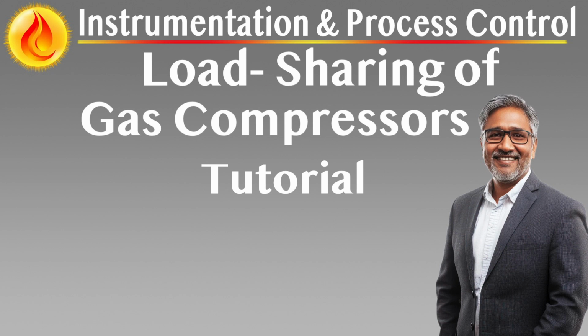2. Predictive rate-based response, POP, detects rapid changes in the control variable by comparing the instantaneous value, CV, against a filtered average, CVFG. The predictive deviation DevPop is computed as DevPop equals CV minus CVFG minus SPPop. If DevPop is positive, i.e. pressure is rising or falling faster than allowed, a predictive response term is added. CRPop equals KPop times DevPop. This term enhances reaction time, preventing system overshoot or undershoot.